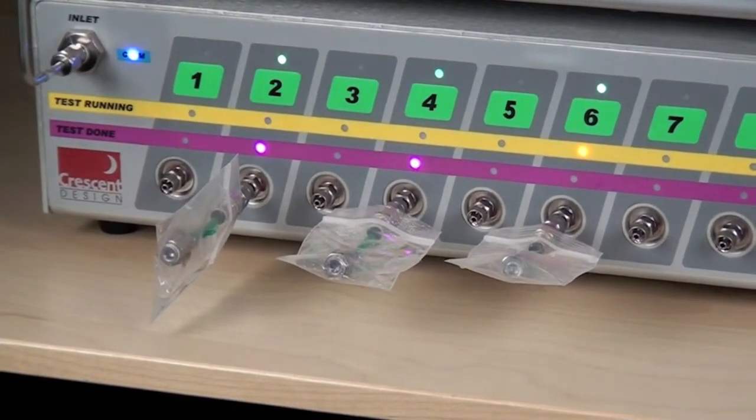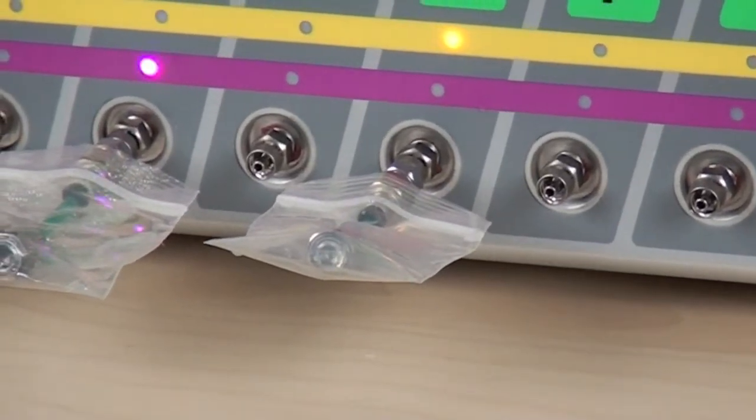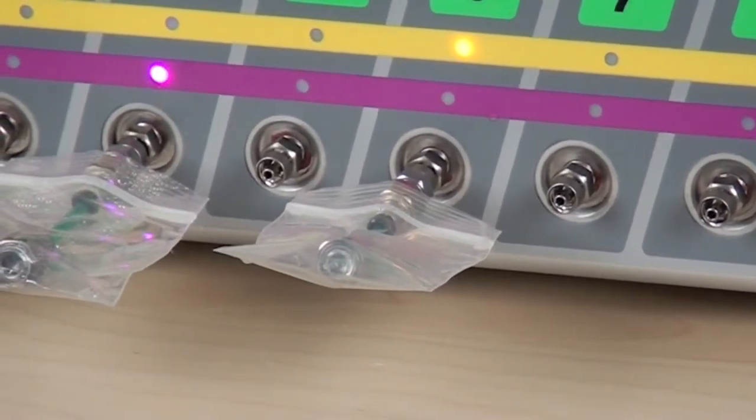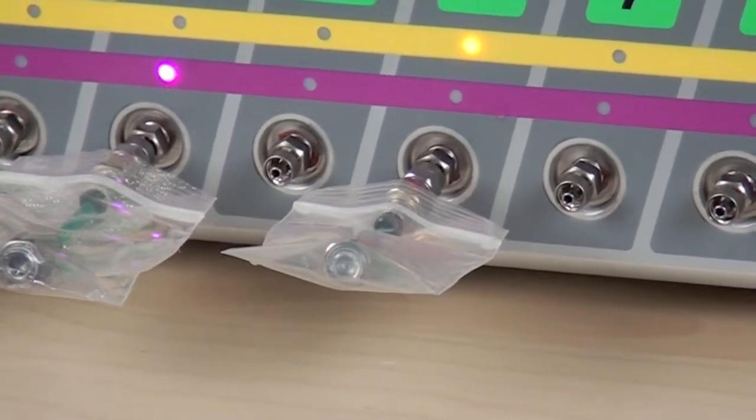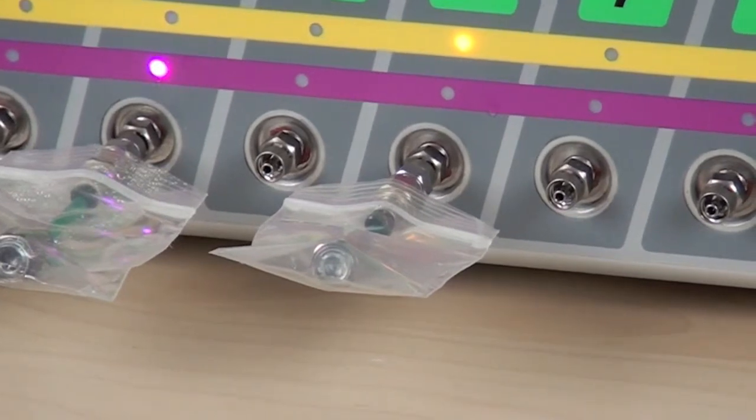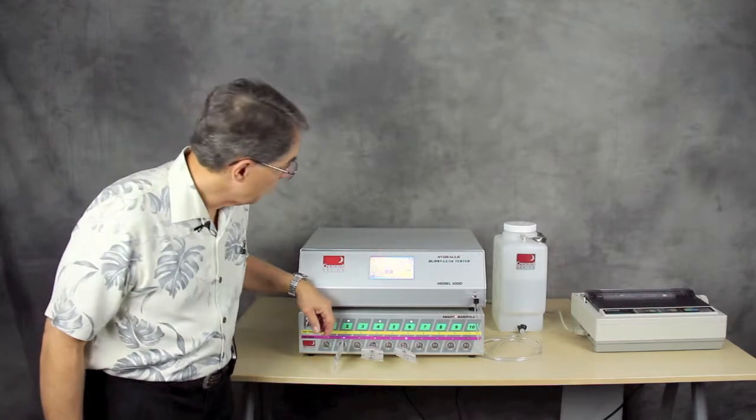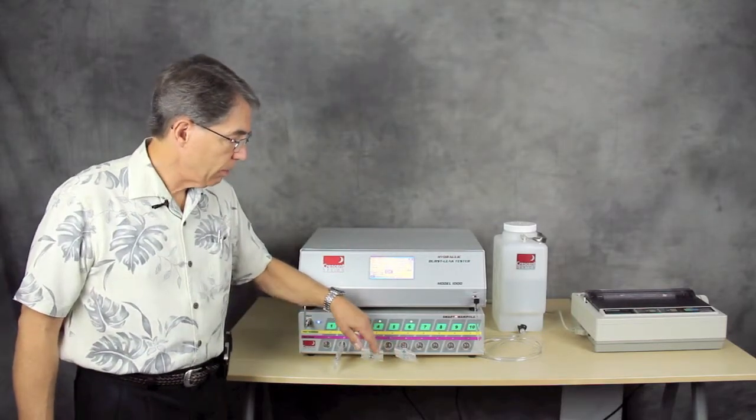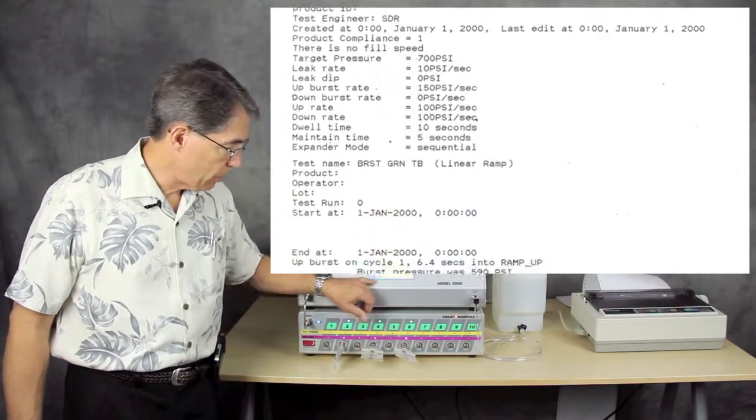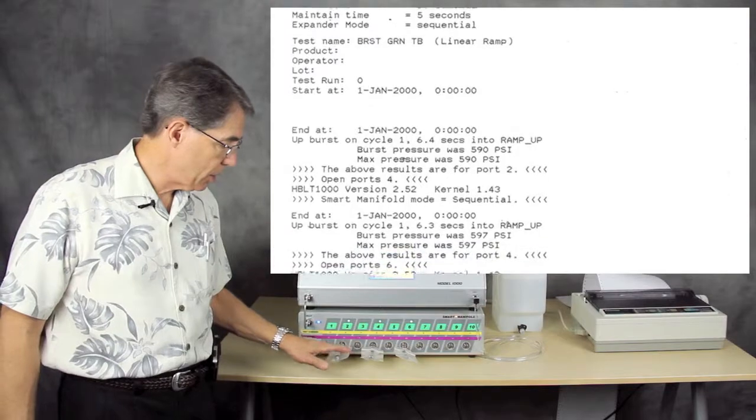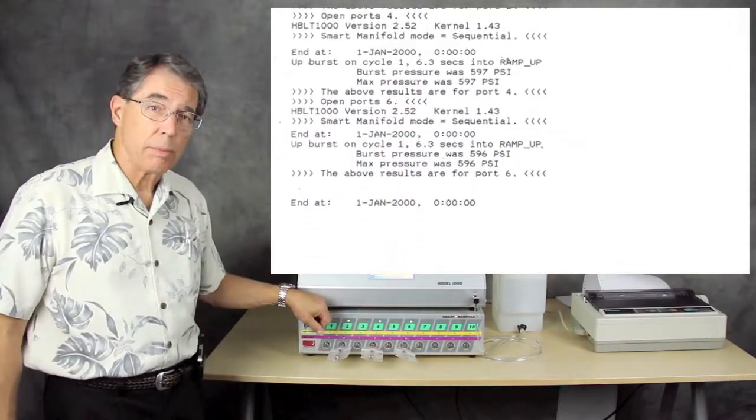The instrument is now preparing itself again. Refilling it, preparing it, and will automatically go to the third port to run the burst test on that channel. And what I see is this one burst at 596 and that completes the sequential burst test and all of the test results have been printed on the printer.